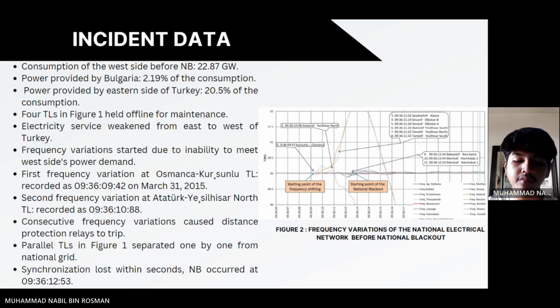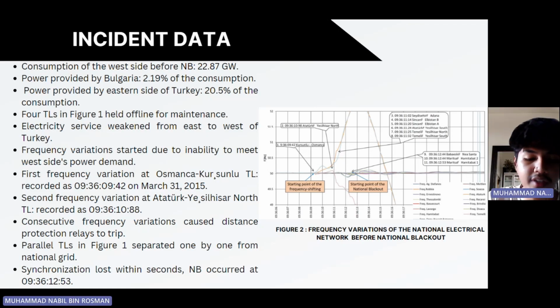After the consecutive frequency variations shown in Figure 2, the distance protection relay tripped due to the factual sequence of events. The parallel transmission lines shown in Figure 1 consecutively separated one after another from the national grid.